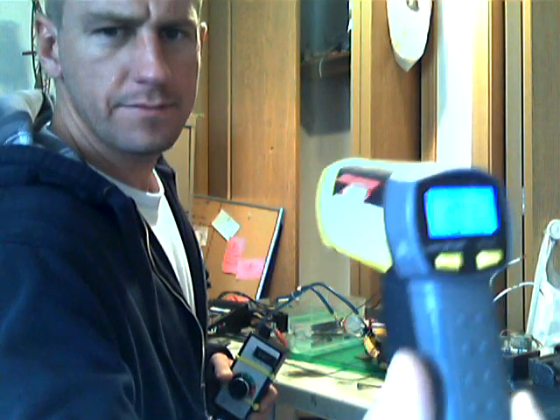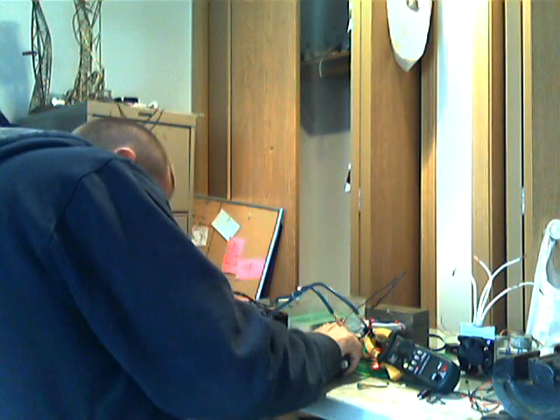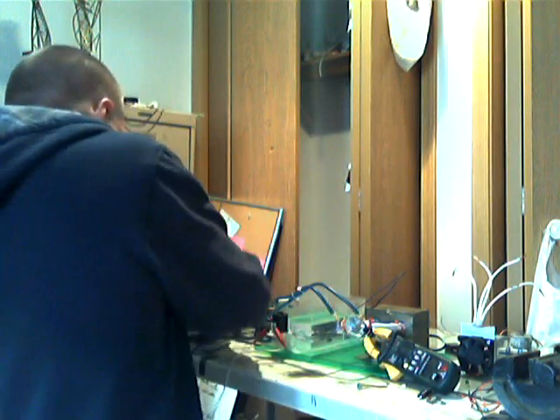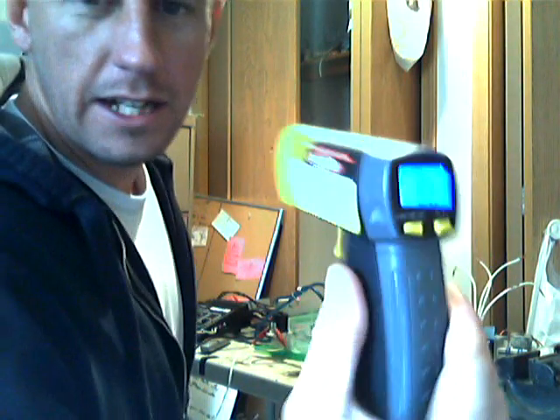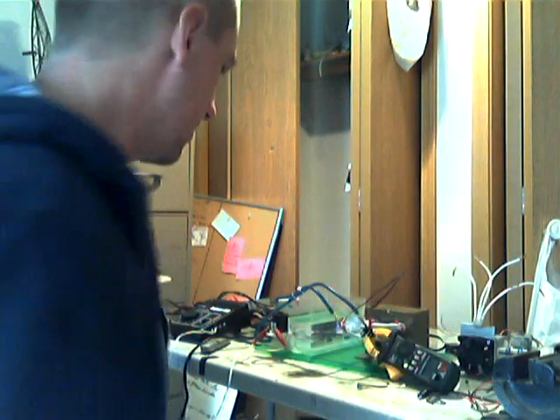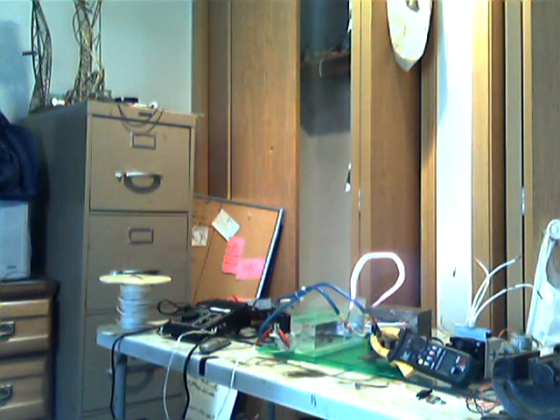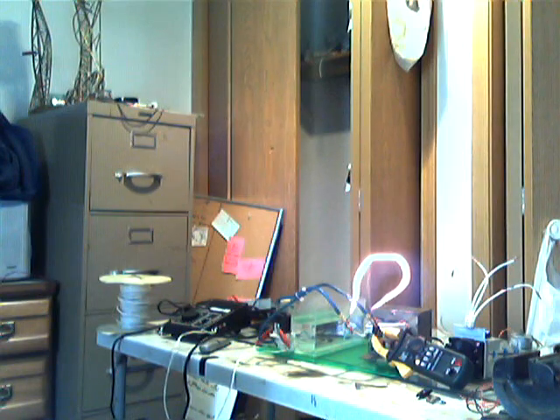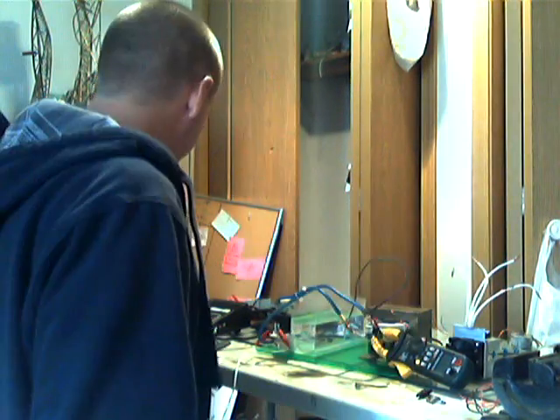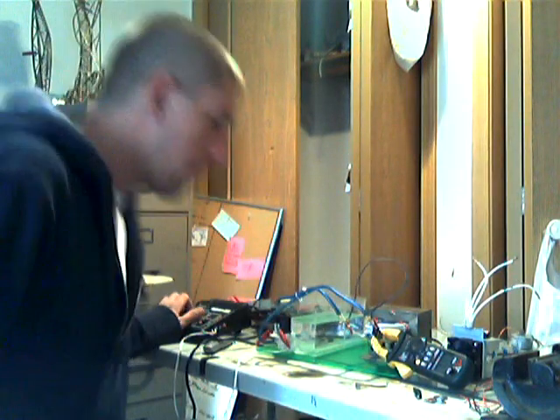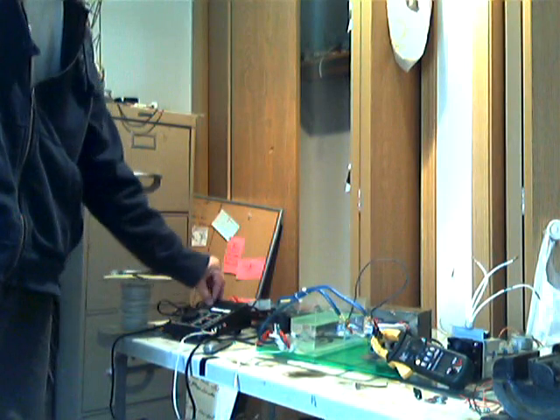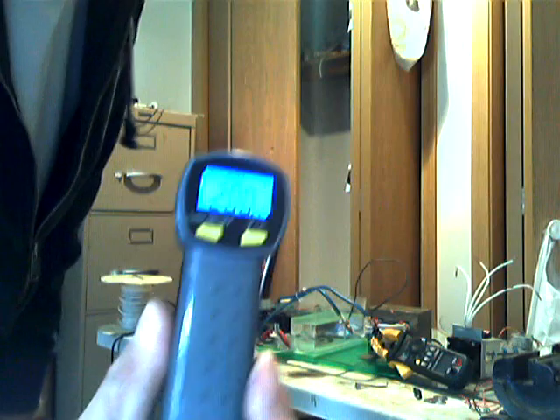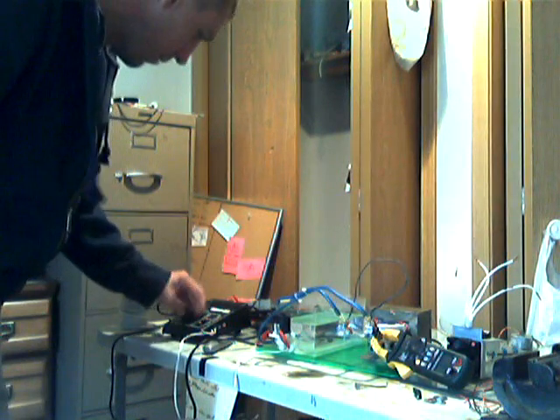Oh yeah, that's hot water. Secondary is at 101 degrees. Primary is at 88 degrees. Now at 200 degrees in my secondary because the breaker blew in my circulation pump.